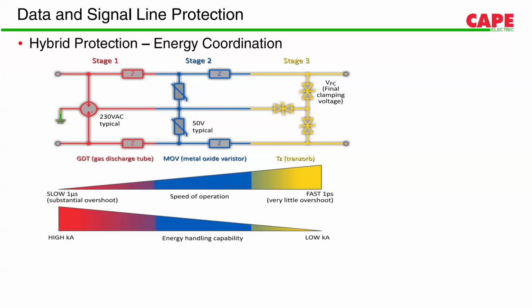So let's say there is a surge. Immediately, our stage 3 diodes operate. Let's say the diode has a voltage protection level of 600 volt, it's just an example, whereas the MOV has a voltage protection level of 800 volt. Once the surge has come, the diode immediately operates and clamps the voltage at 600 volt, but we have to ensure that the MOVs also operate. The MOV has a higher voltage protection level, in this example around 200 volt more than the diode. So how do we ensure that the MOVs also operate on time?